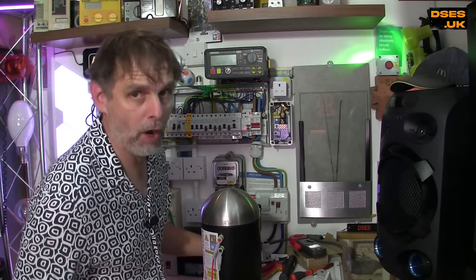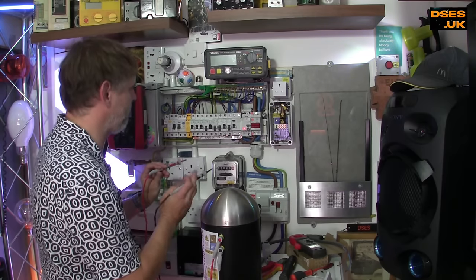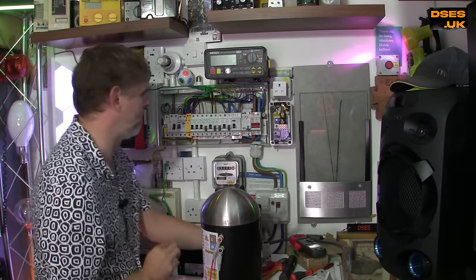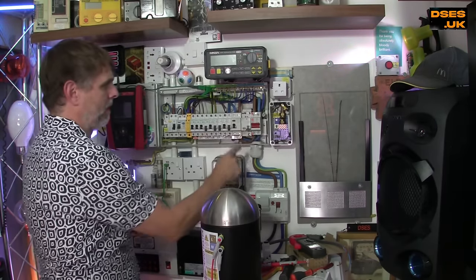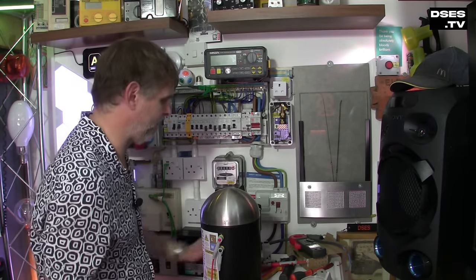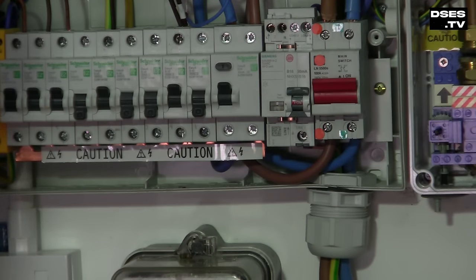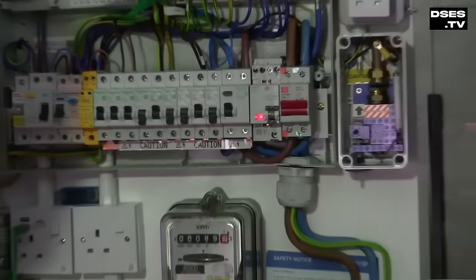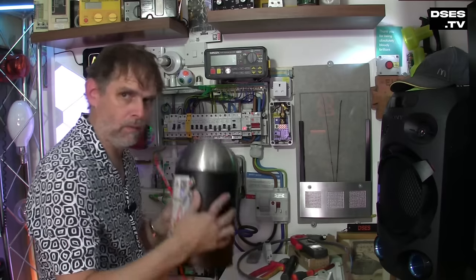Let's repeat our testing in reverse order. We'll start with the AFDD tester — the Siemens is live again. I'm going to put that between line and neutral, and it should — there you go — trip off. That's because of the fixed arc gap in there. That won't go back on until I hit the reset button, and it'll come back on flashing a yellow light to say that's an arc fault. There you go — a close-up of the yellow light. Pushing that resets the indicator back to red. Successful series arc test with my AFDD tester.